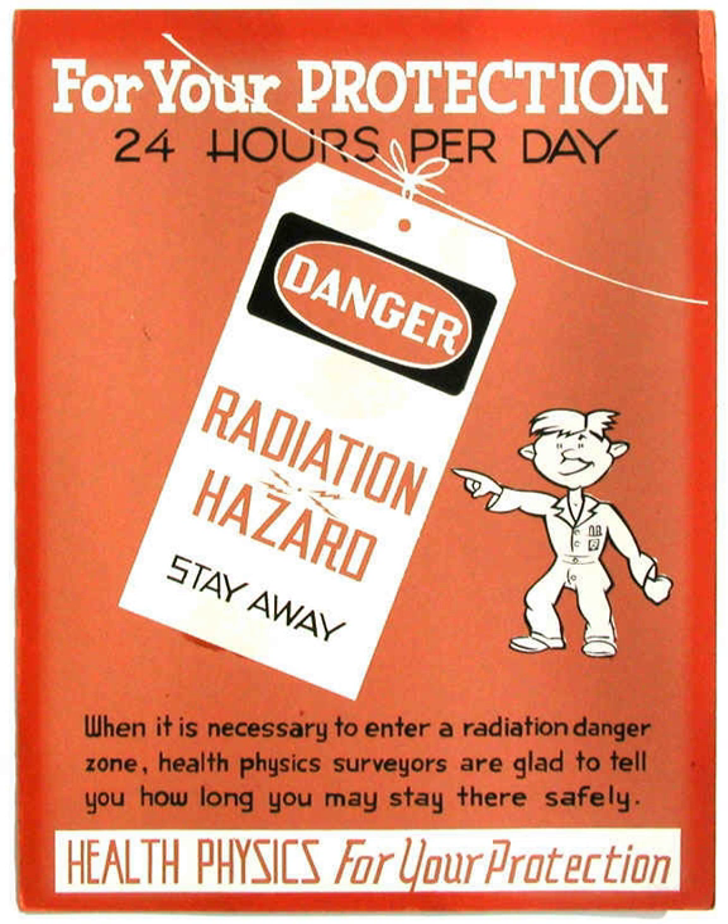Practical ionizing radiation measurement is essential for health physics. It enables the evaluation of protection measures and the assessment of the radiation dose likely or actually received by individuals. The provision of such instruments is normally controlled by law — in the UK it is the Ionizing Radiation Regulations 1999. The measuring instruments for radiation protection are both installed in a fixed position and portable.